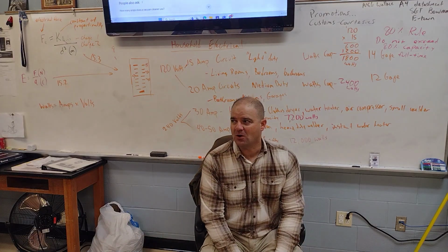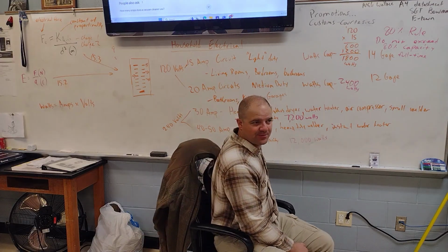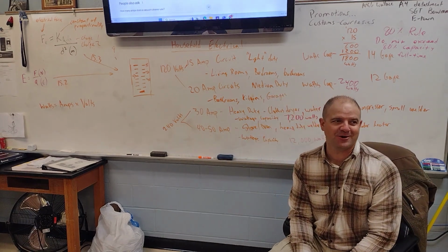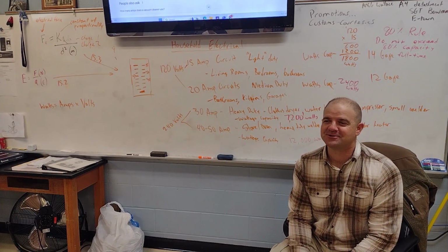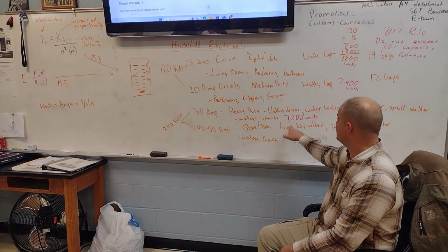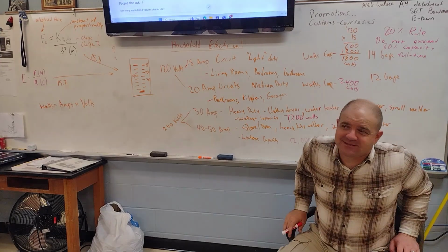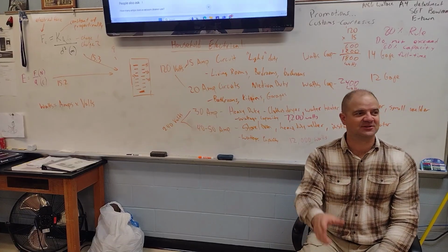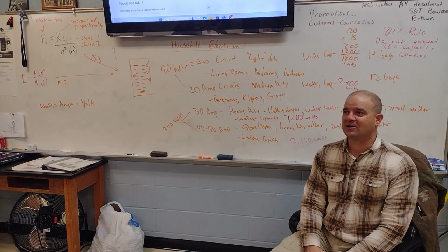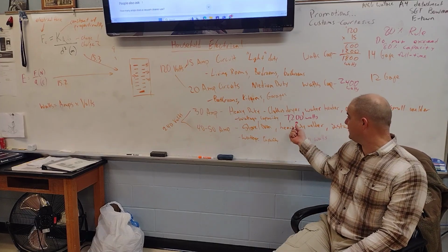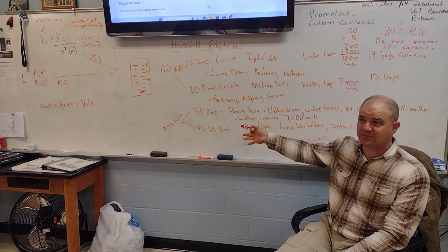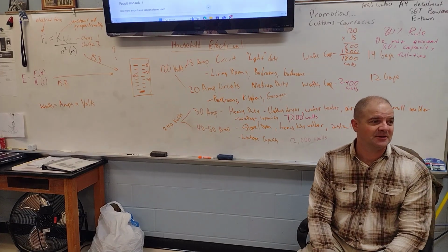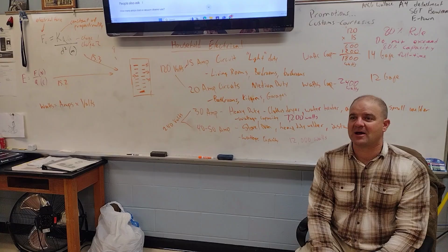5,760. So if our 30 amp circuits in our homes are meant to run our clothes dryers, and the capacity is 7,200 watts, my guess is if we went home and looked at our clothes dryers, that little placard on them that tells you the electrical information, I will guarantee you, if it's a 30 amp circuit, it ain't running at 7,200 watts. It's probably running around 5,000 watts. If it's on high, it's probably drawing 5,000 watts.